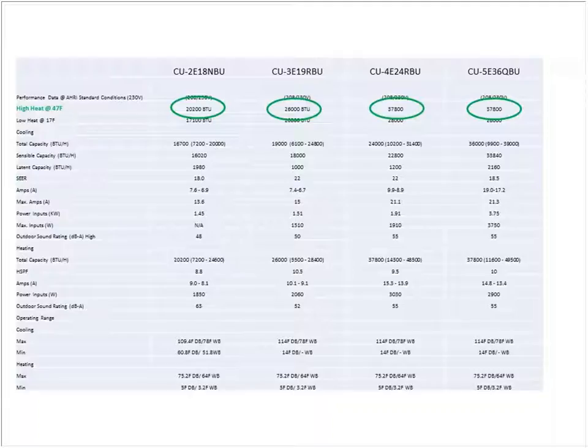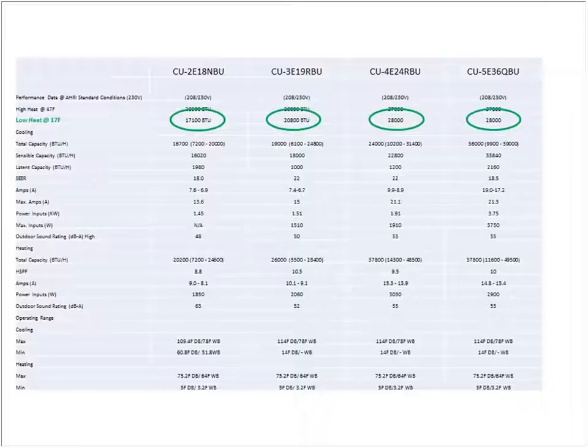So key components for multi-zones, again, there's your output and heat. And I'm kind of biased towards heat here in the Northwest because that's what we do. But here's your high heat, and they all perform pretty darn respectable at 47 degrees. But my concern typically comes down to what's the output at 17 degrees. So when I talk about sizing, and I try to stay away from being the official sizing, I look at what my heat load requirement is at low temperature. It wouldn't do me any good to put a 28,000 BTU at 17 degree unit in if I need 36,000 BTUs. So that is going to be kind of a conflict, right?